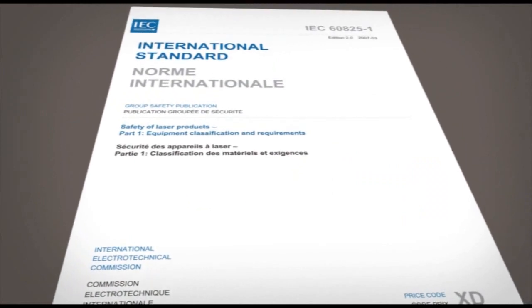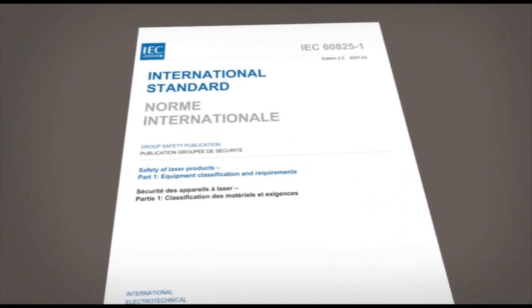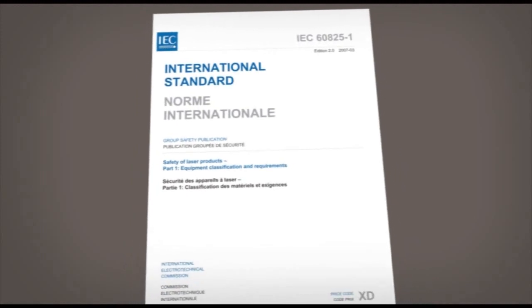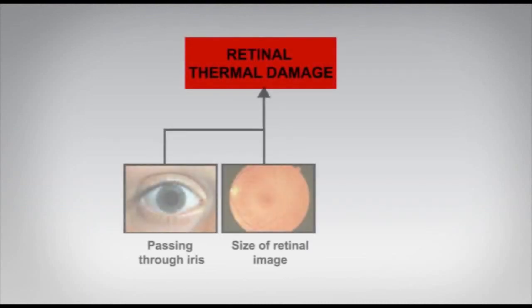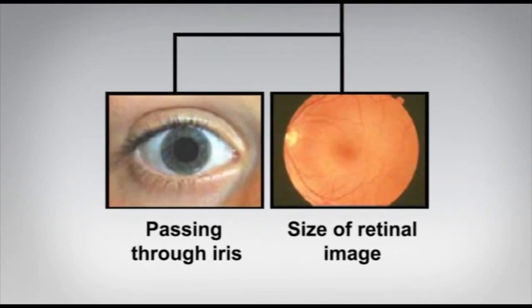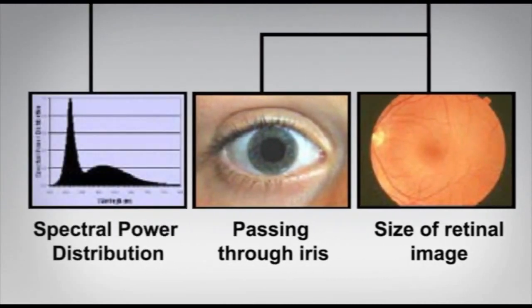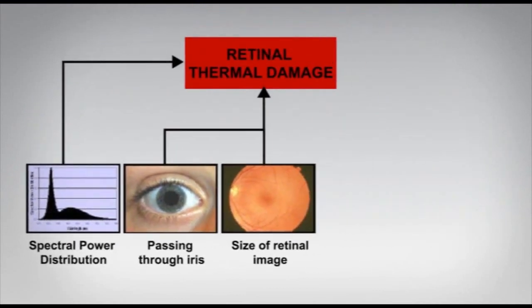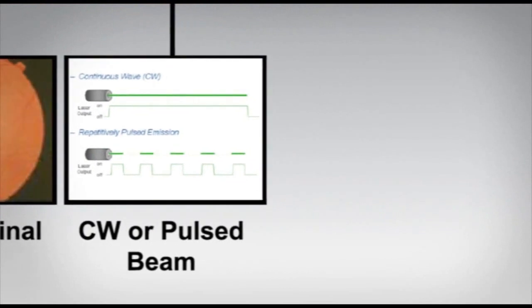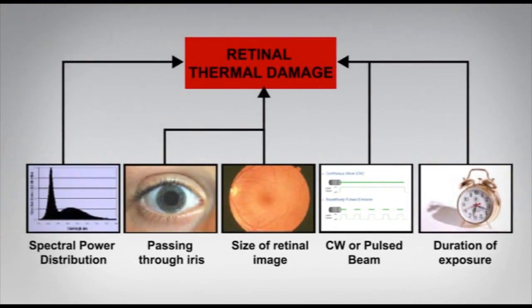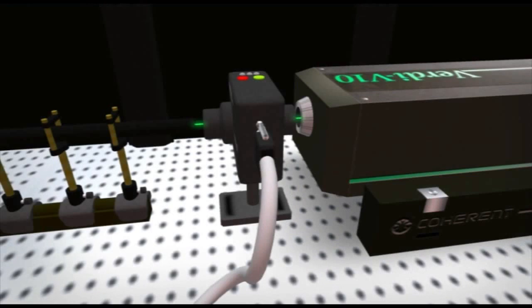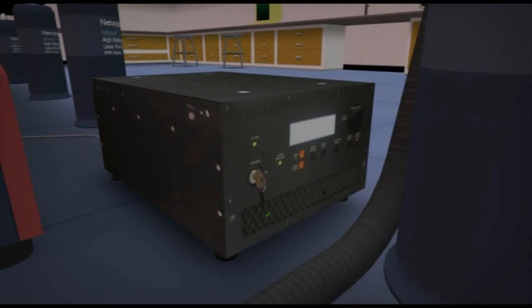Lasers are classified using this standard based on the hazard they can potentially produce. However, the level of hazard is not solely governed by the laser's power or energy. It is also dependent upon other laser beam properties, which determine the potential size of an illuminated spot on a human retina and the power density of a spot on the skin. Other factors that affect laser classification include the pulse characteristics and the wavelength of the laser light, which both determine the human damage mechanism, how long people are likely to be exposed to laser light, and single fault conditions, such as power supply surge and control measure failure.